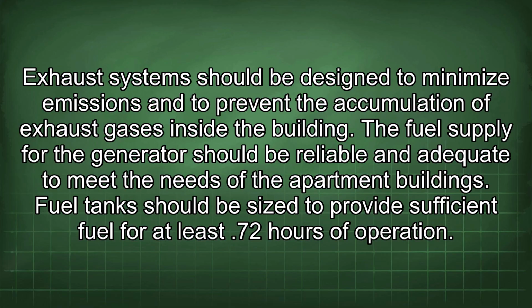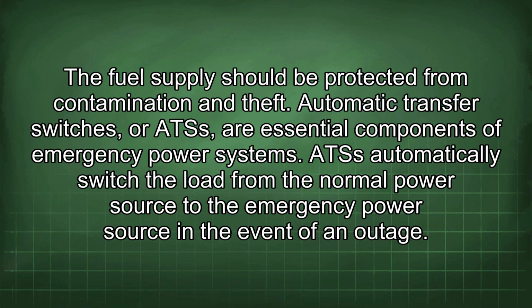The fuel supply for the generator should be reliable and adequate to meet the needs of the apartment buildings. Fuel tanks should be sized to provide sufficient fuel for at least 72 hours of operation. The fuel supply should be protected from contamination and theft.